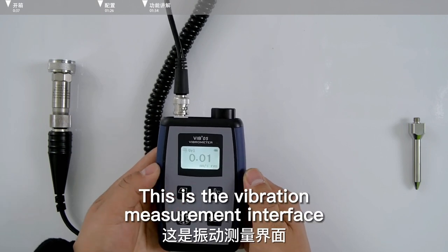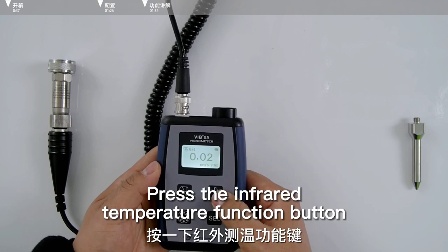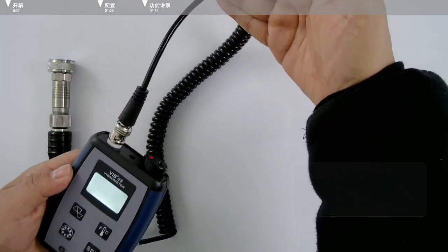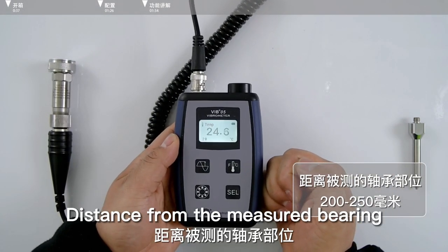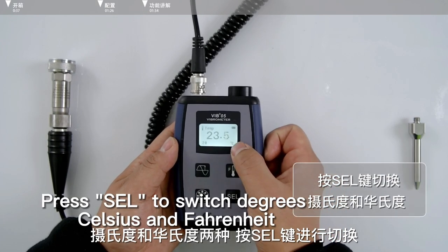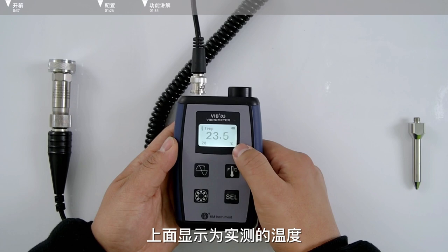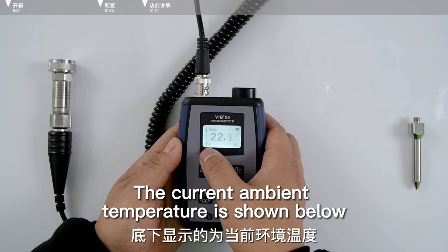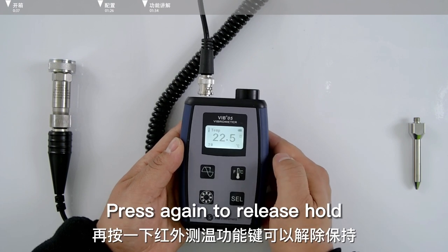The second function is infrared temperature measurement. Press the infrared temperature function button and infrared laser spots — a red dot — appear on the instrument. The effective testing distance from the measured bearing is 200–250 mm. Press SEL to switch between degrees Celsius and Fahrenheit; Celsius is recommended for routine testing. The actual measured temperature is shown above and the current ambient temperature is shown below. Press the infrared temperature function button to hold the temperature reading; press again to release hold.